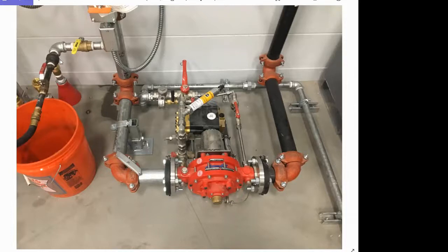This here is just a test port that we use after we run the system - we have a solution. It comes out through the hose, we collect it in the bucket, and then we run refractometers to test to make sure it's actually proportioning at the design rate, which in this case is 3% for lithium-ion batteries.